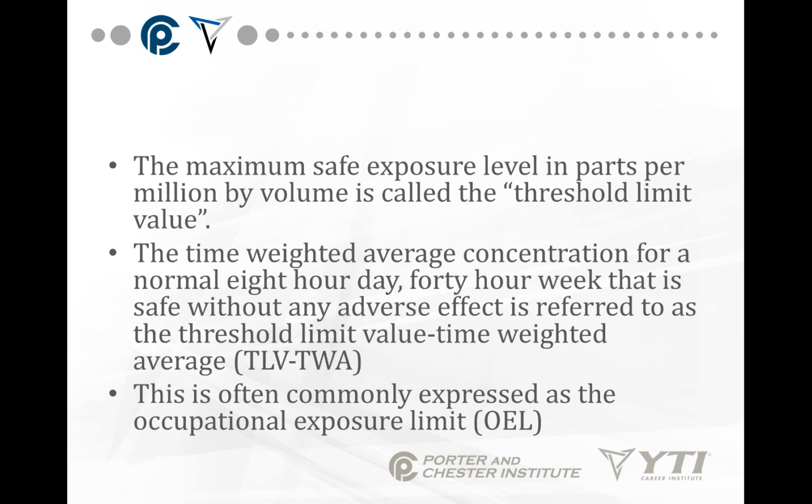The maximum safe exposure limit in parts per million by volume is called the threshold limit value, or TLV. The time-weighted average concentration for a normal 8-hour day, 40-hour week that is safe from any adverse effects is referred to as the threshold limit value time-weighted average. This is often commonly expressed as the occupational exposure limit. Again, we're talking about an 8-hour day, 40-hour week, because that's what most people work in an industrial environment.